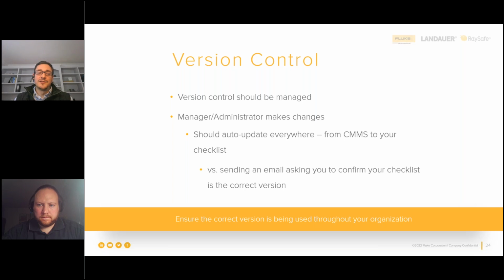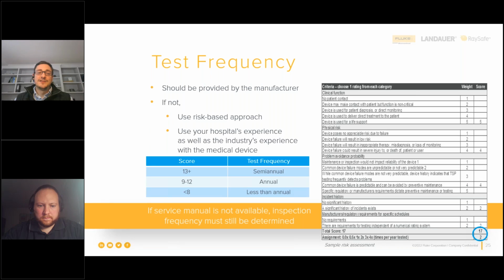The other part of a good procedure is how often you're going to run that procedure. So you have to determine a test frequency. This should be in your service manual, but if it's not, right, you should take a risk-based approach, which is here on the right side of this slide. So this takes into consideration the criticality of the medical device, the risk that a failure might have to the facility, the probability that a failure could occur in your hospital's experience, and also the industry's experience with that medical device. If you take all of those things into consideration, that can also produce a risk-based assessment of how often you should be testing that medical device. So do know that there are options out there if the service manual doesn't provide anything to you.